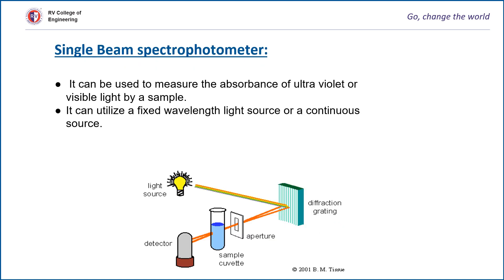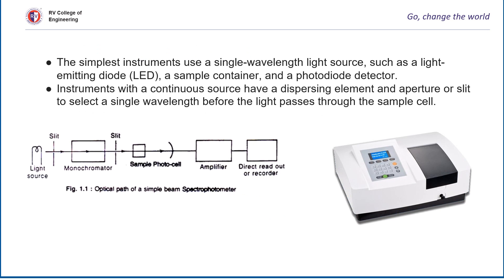There are two types of spectrophotometer: single beam and double beam. The single beam spectrophotometer can be used to measure the absorbance of ultraviolet or visible light by a sample. It can utilize a fixed wavelength light source or a continuous source. It is similar to a colorimeter. The simplest instruments use a single wavelength light source such as a light emitting diode, a sample container, and a diode detector. Instruments with a continuous source have a dispersing element and aperture or slit to select a single wavelength before the light passes through the sample cell.